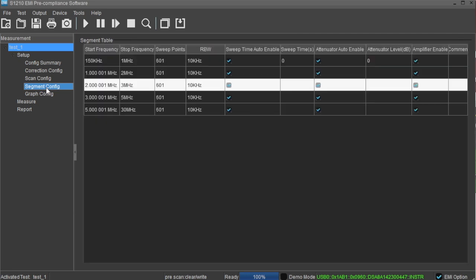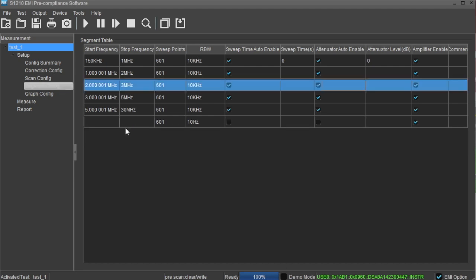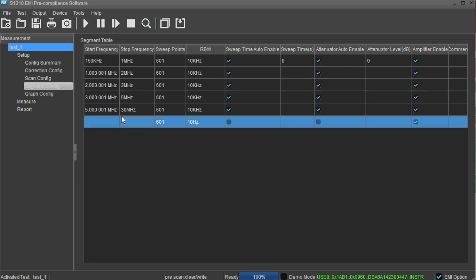The segment config area is where you can configure each scanned segment. It contains the start and stop frequencies for each step, sweep points, as well as the resolution bandwidth setting for each step. You can add and delete segments by simply right clicking in the segment window and then entering the proper values in each field.